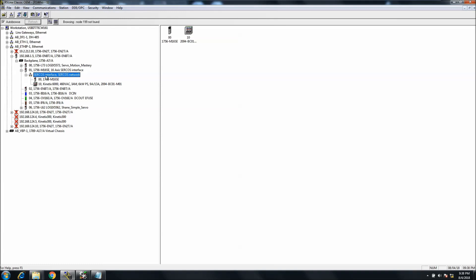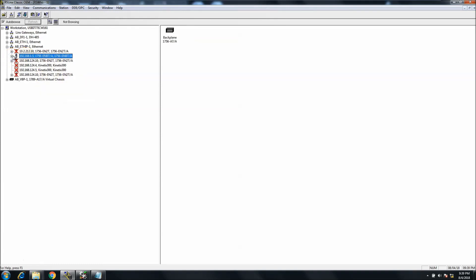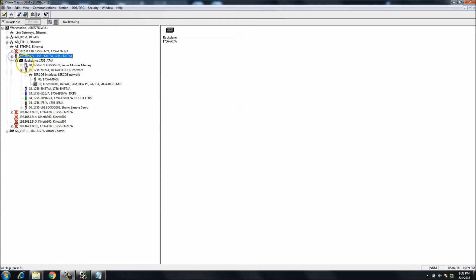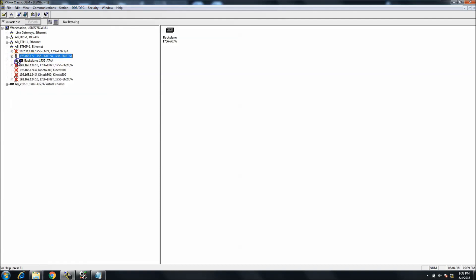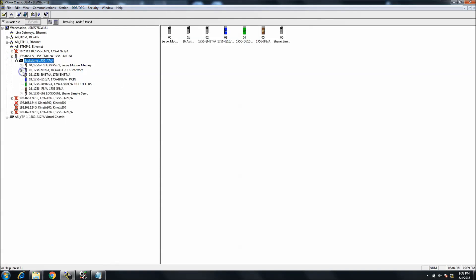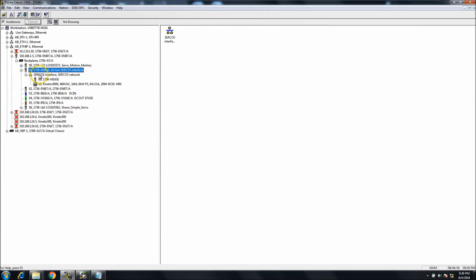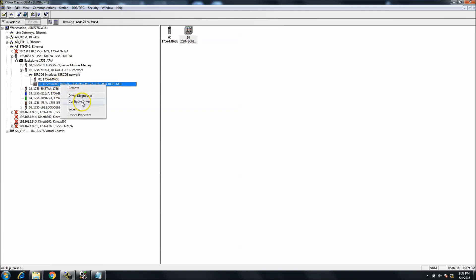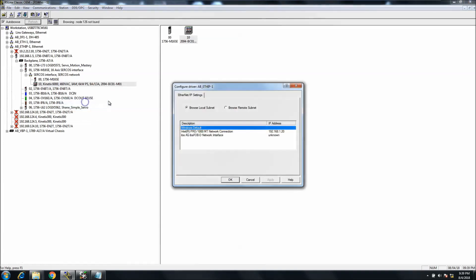Now with that said, you drill down to your card you're using, then it shows your backplane. In your backplane, you would look for the 1756-M16SE, which would basically be your SERCOS network. You drop that down and then you would see your Kinetix servo drive.